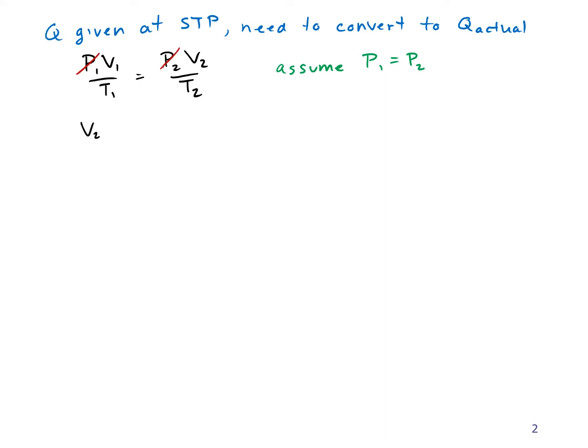Now I'm going to solve for V2, which equals V1 times T2 over T1. So that's a volume. The flow rate Q is just a volume per time, so I can divide everything by time and say that Q2 equals Q1 times T2 over T1.